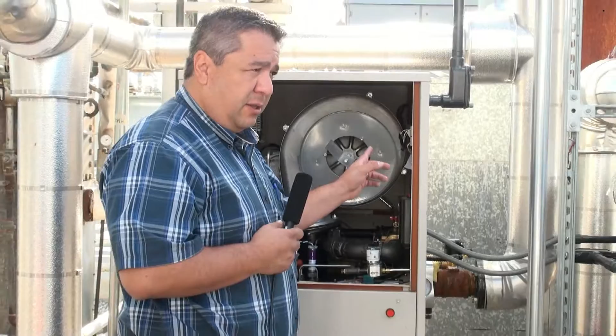So throw the switch. I'll show you in the back right now. There's the total power disconnect in the back. It's a little box with a little light switch. That turns the entire power off to the unit. So we've got the disconnect, and that's really the only way to turn the boiler off with that switch. You're being automated, so he can enable or disable the boiler, do everything he wants. There's Modbus automation to it.